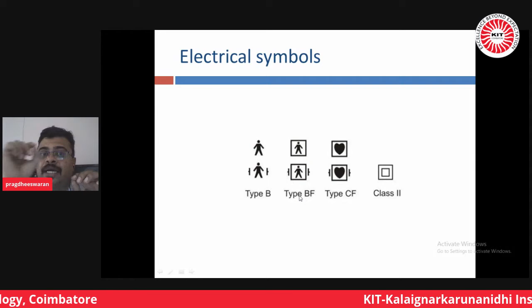In the hospital, they are not maintaining the earth. Some problem, so the leakage current goes above 200 microampere to the ECG machine or something, which causes the problem. So whenever you calibrate the equipment as per NABL, you did it.